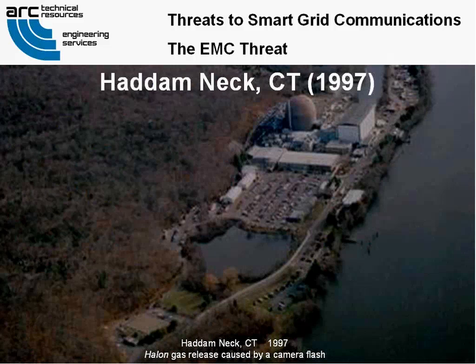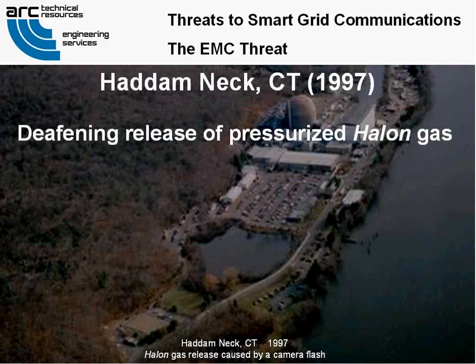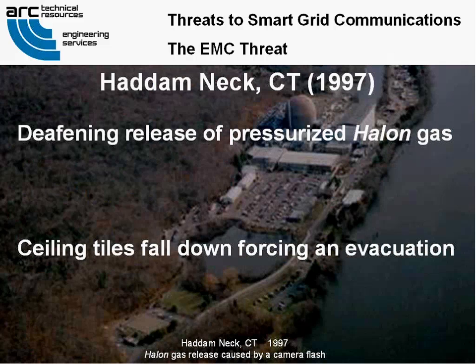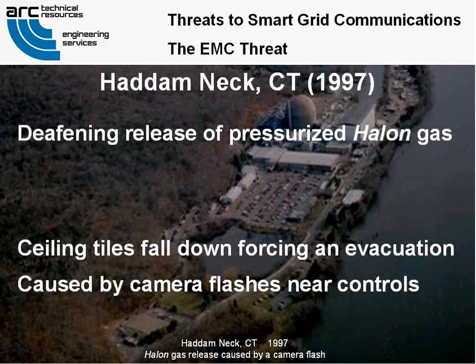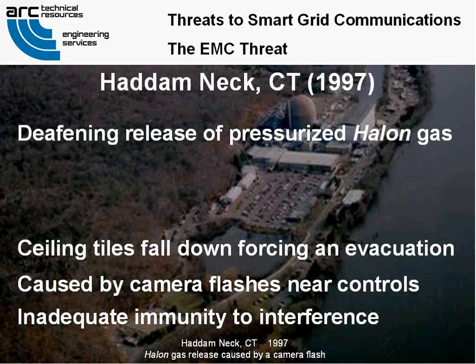Haddam Neck, Connecticut, 1997. A deafening release of pressurized halon fire suppressant gas occurred in Connecticut at the Haddam Neck plant, causing the ceiling tiles to fall into the control room and all of its occupants to be evacuated. It was caused by camera flashes from the photographer taking pictures in the control room. Inadequate immunity to common sources of interference causes unacceptable failures such as this. Those darn photographers. Shouldn't let them in the control room.